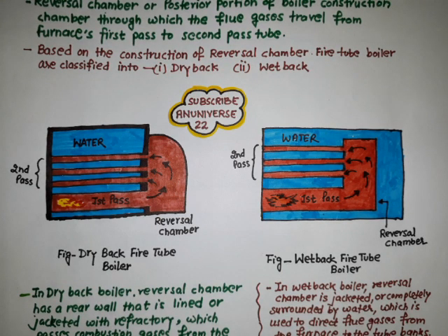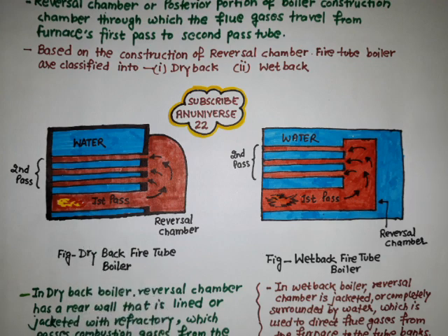In the dry back boiler, only the tubes are surrounded by water, not the reversal chamber. It uses a common rear tube seat and features convenient fire side and water side access. However, it has a large functional footprint due to its heavy vessel-sized rear door, which requires sufficient space to open and a cool-down period before opening. Dry back boilers also require regular refractory and tube seat inspections, which can be costly maintenance items.